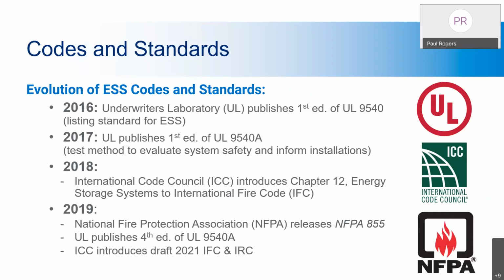We're now currently on the fourth edition of UL 9540A, and it has continued to go in the right direction where these batteries are really being put to the test. We really want to know in UL 9540A what happens if they do fail. It's a destructive test, and they actually look at how the batteries fail and what comes off the batteries, and whether the installation requirements and the fire protections put in place are going to be able to manage those things if they were to fail.